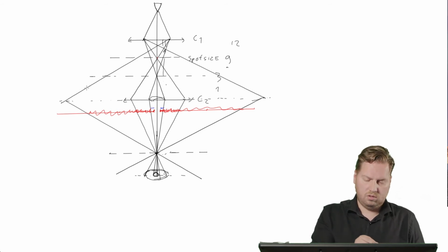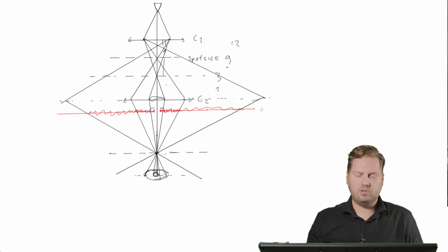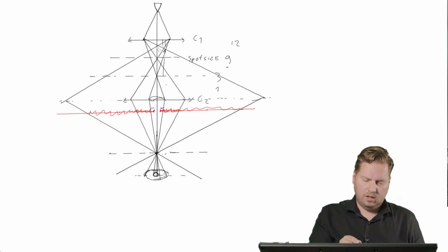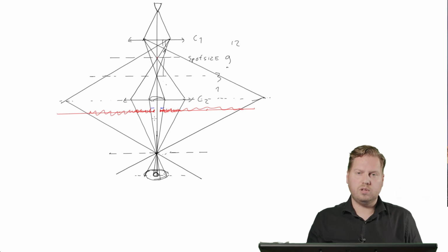The beam is bent stronger, and therefore the aperture that is behind your C2 will block more of the light, or more of the electrons that are coming out of your C2 lens. So what effectively happens when you change the spot size from a small number to a large number for TEM is because the beam is spread so far, the aperture is blocking a larger percentage of the electrons that is allowed to pass through this aperture coming from the C2 lens.